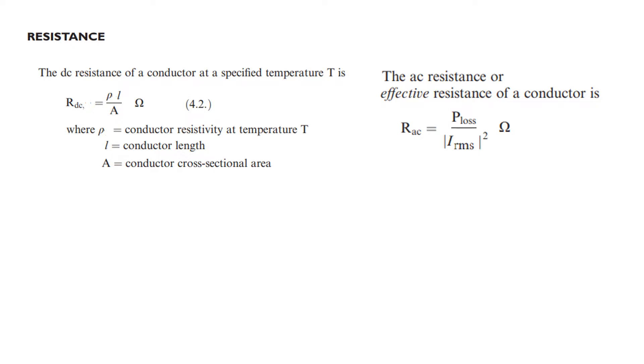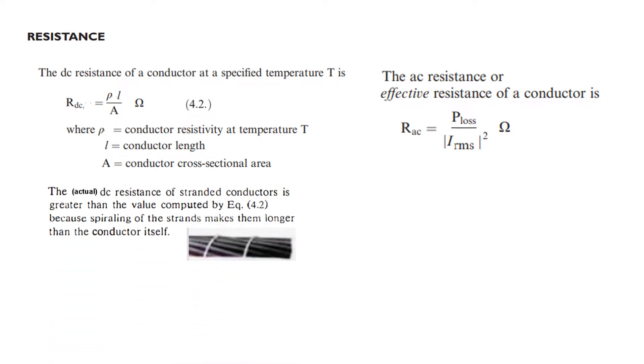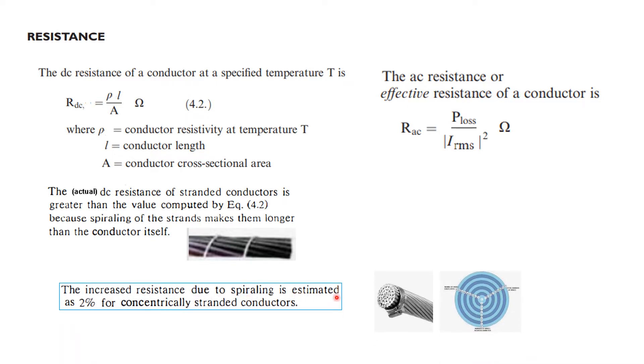The actual DC resistance of a stranded conductor is greater than the computed value. When we calculate the length, the actual length is greater than L because of spiraling. The increased resistance due to spiraling is estimated to be 2% more, so the length is 2% more. We multiply by 1.02 to get the actual resistance. This applies to the concentrically stranded cable.